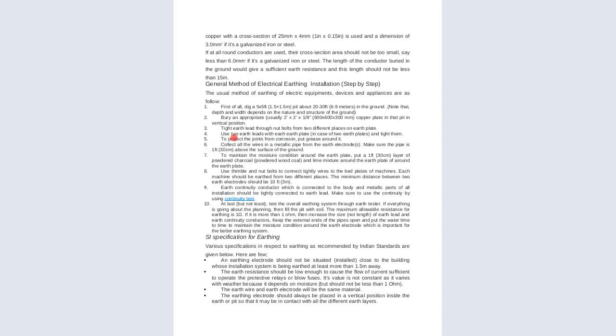And then step 4 is to use the earth leads with each earth plate, that is in case of 2 earth plates, and tighten them. To protect the joints from corrosion, put grease around them. Another step is to collect all the wires in a metallic pipe from the earth electrode. That is, make sure the pipe is at least 1 foot above the surface of the ground. Step 7: to maintain the moisture condition around the earth plate, now put a 1 foot layer of powdered charcoal. The powdered charcoal is just the normal charcoal that we use, and a lime mixture around the earth plate.